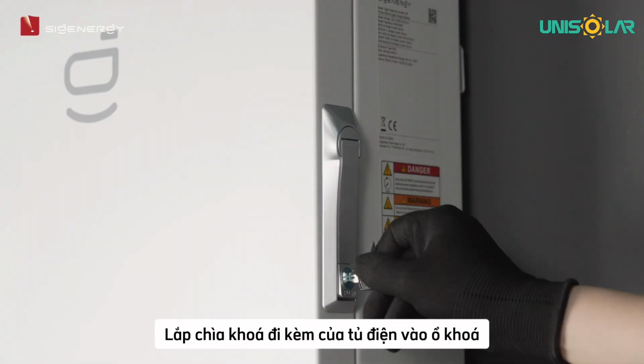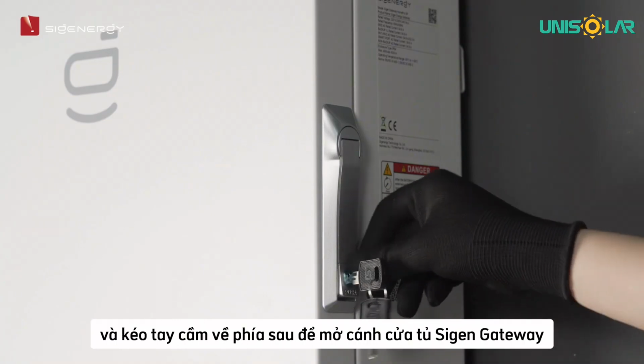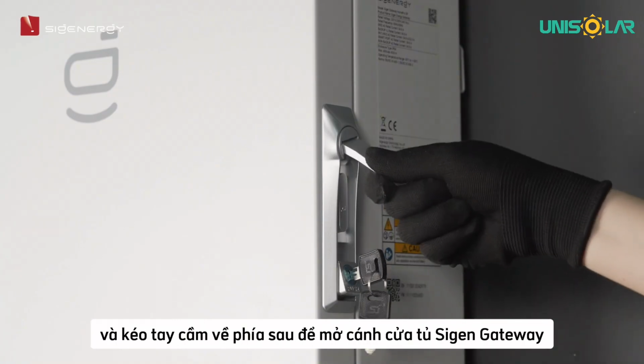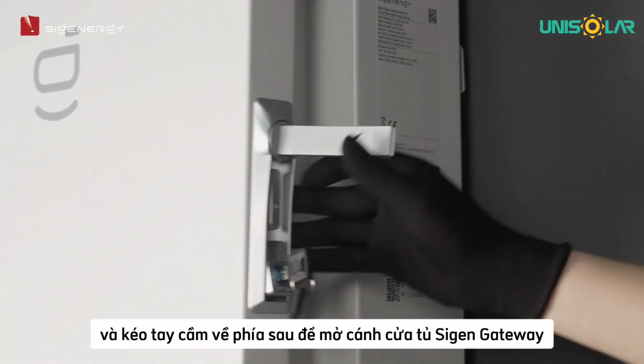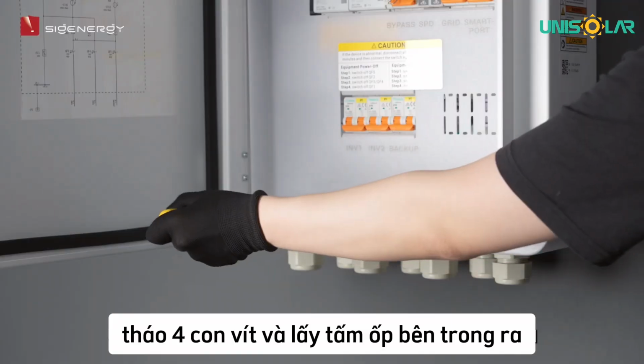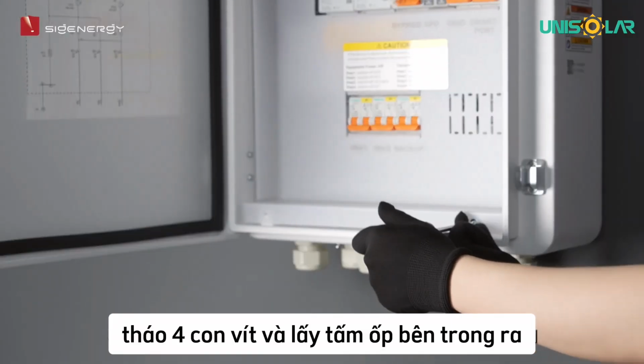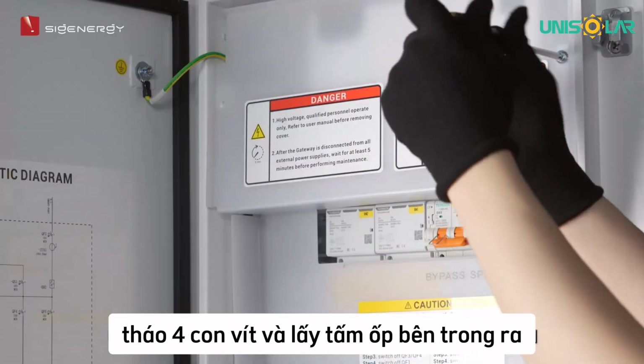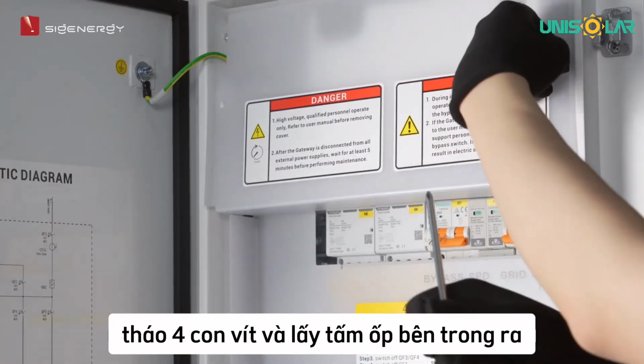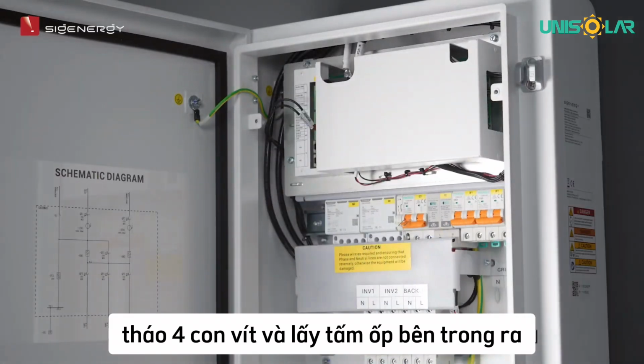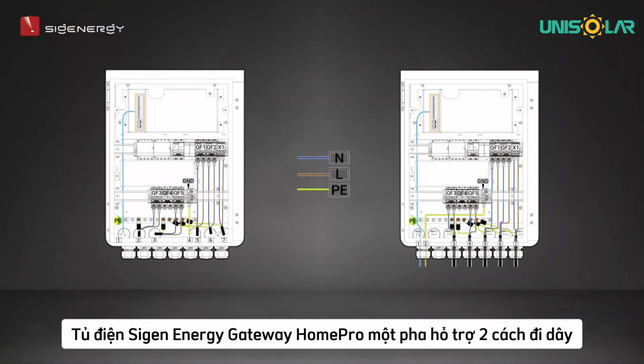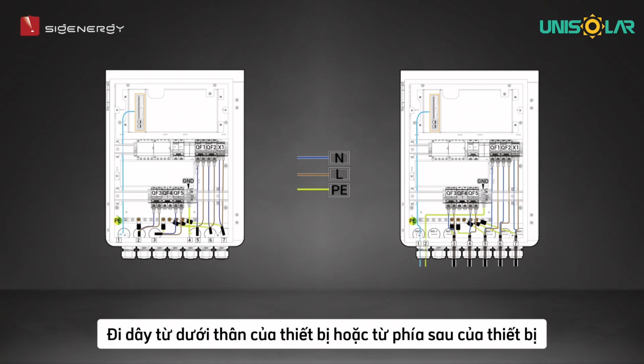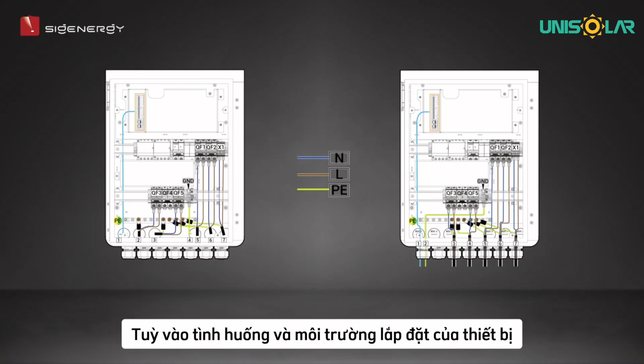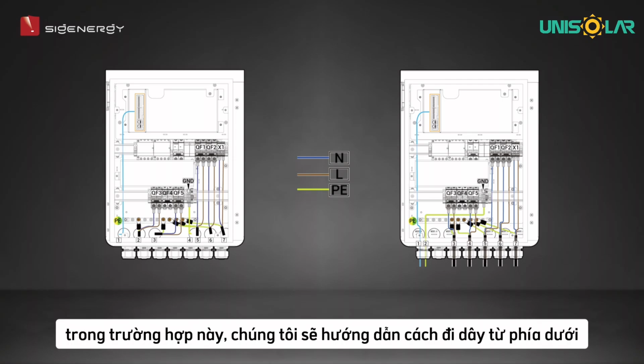Insert the key, turn it in the lock cylinder, and pull the handle backward to open the gateway. Unscrew the 4 screws and take out the inner panel. Sigenergy Gateway HomePro single phase supports 2 wiring options, bottom wiring and back wiring, adapting to different installation scenarios. We take bottom wiring as an example.